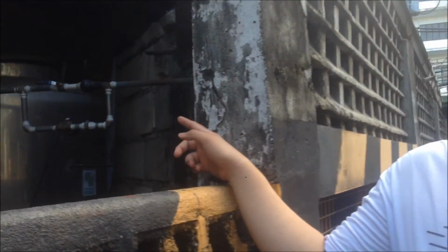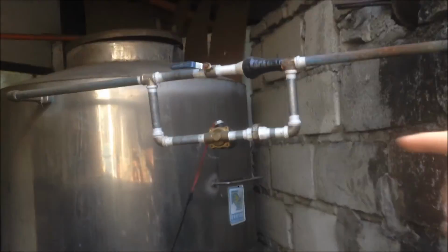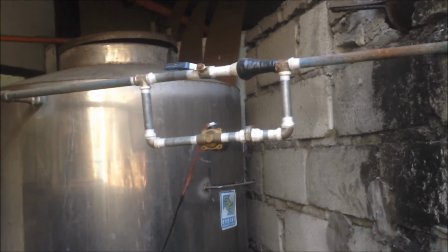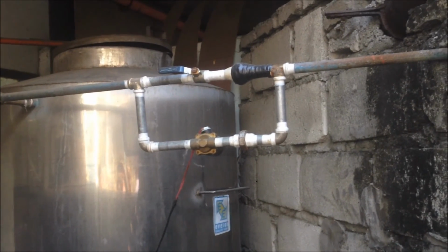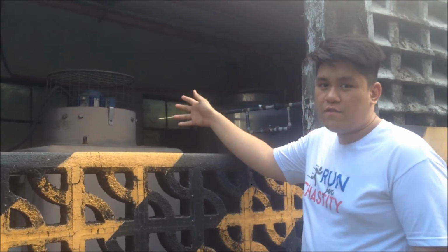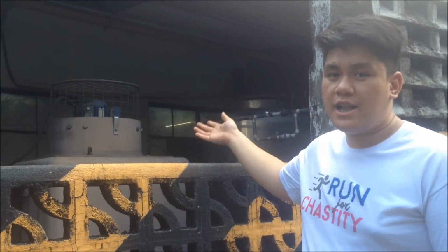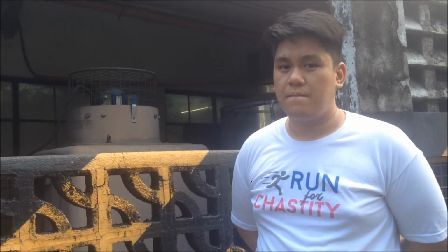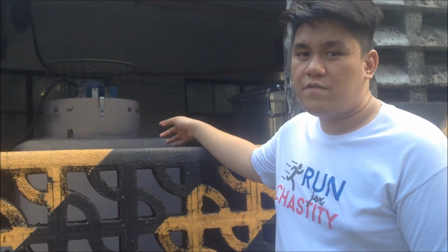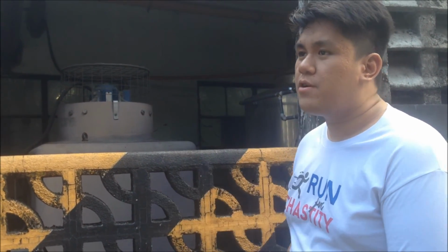Adjust the rate accordingly per your local water quality and evaporation rate regulations, preventing accumulation of solids in the circulating water. Routinely check the oil of the motor and the shaft alignment in order to secure its safety and stability. Lubricate fan shaft bearings every 3 months to maintain proper operation.